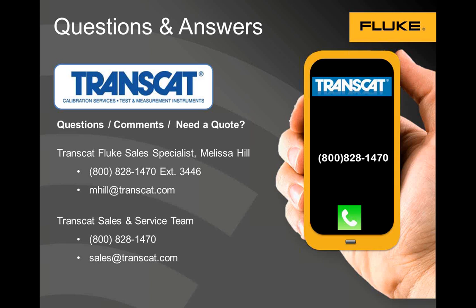How many Fluke instruments can connect to the app at one time? How many readings can I see simultaneously? As I talked about briefly in the presentation, the goal is to have 20 instruments displayed. That's a lot, more balls than I can keep up in the air, but right now you're limited to 11. Ten of them would be through Bluetooth. It's not Bluetooth, it's Bluetooth LE, low energy. Then the infrared cameras have Wi-Fi, 802.11. So you have up to 11 different instruments, each being displayed on one screen.